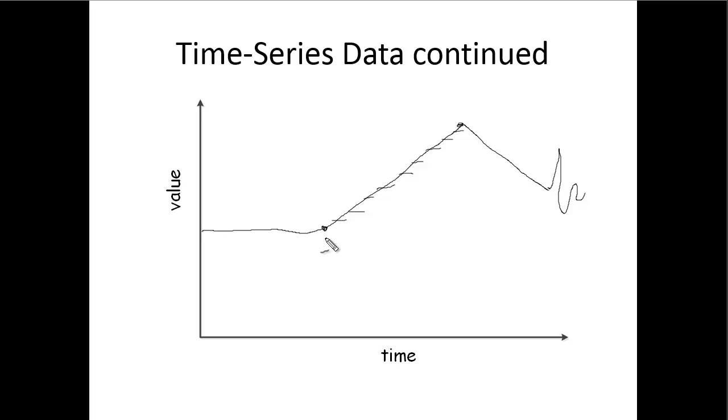Okay, and so there's this algorithm called the swinging door algorithm. And so what I do is I take 2 points and I establish a slope, okay? And then I've got a deadband outside of that. And I say as long as my point's coming along here or inside that deadband, I'm going to ignore them.